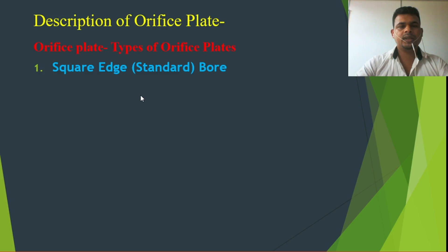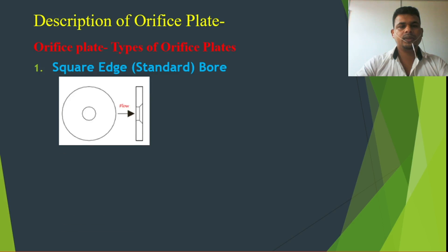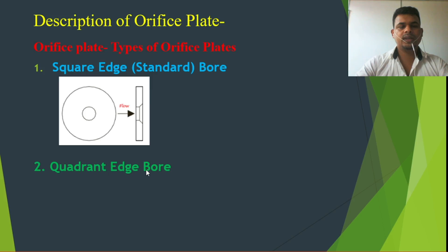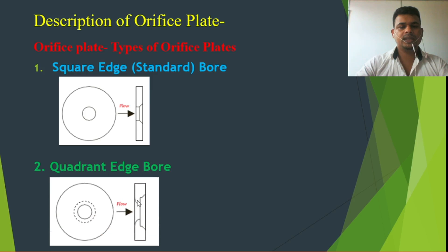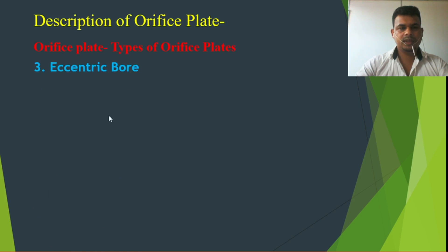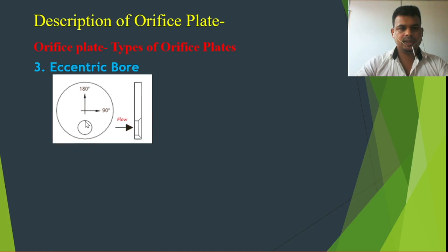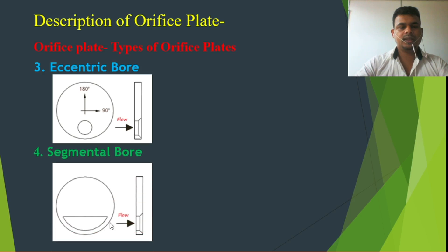The square edge bore, also called the standard bore, has the bore at the center of the orifice plate. The quadrant bore has a tapered entry. The eccentric bore is offset from the center to one side. The segmental bore is a segment of a circle. Each different type of bore has a different purpose of use.